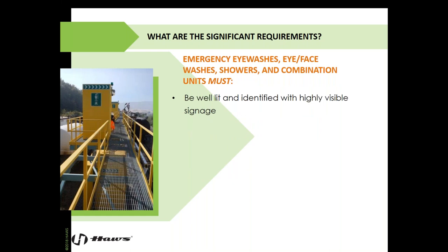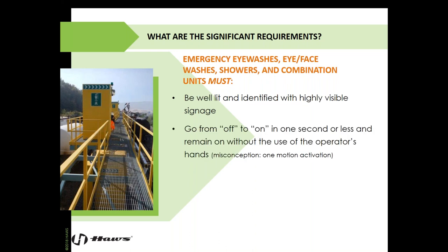Moving on, the area needs to be well lit. It needs to be identified with highly visible signage. Again, referring to the left, you can obviously see the booth is pointing to which direction the door is in. It has a sign telling you there's a shower and there's an eye face wash in this location. The unit needs to go from off to on in 1 second or less, and it needs to remain on without the use of the operator's hands. Both of these are very important.